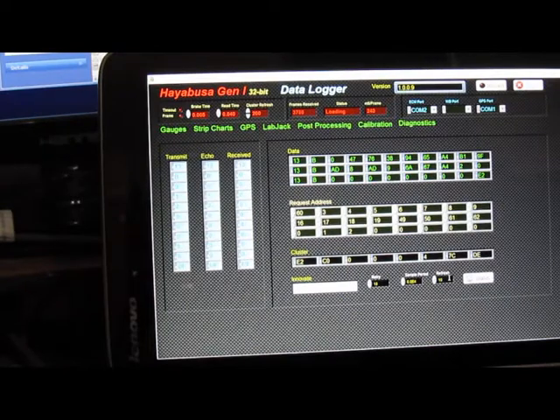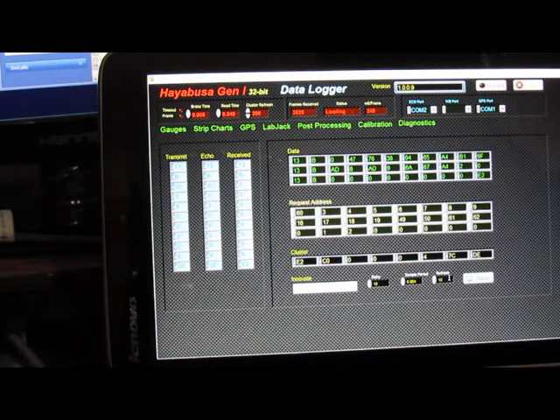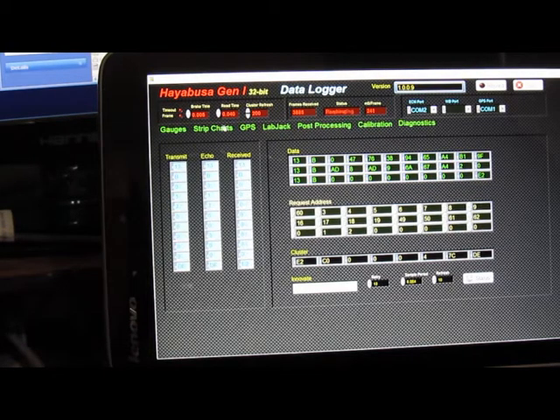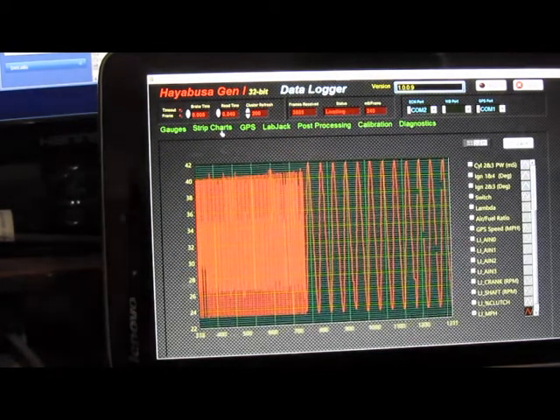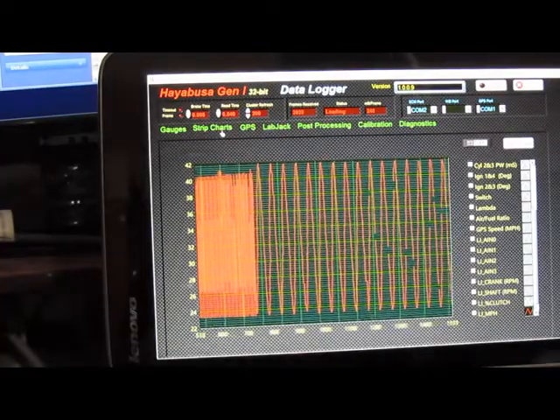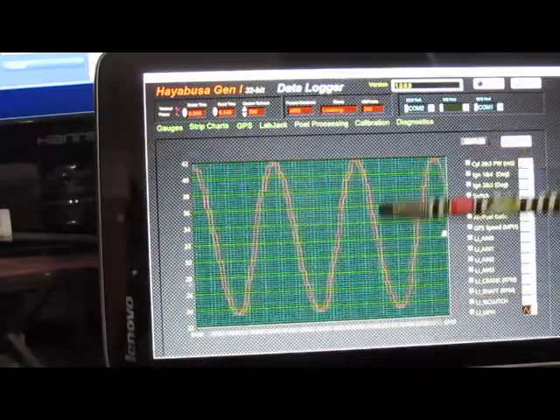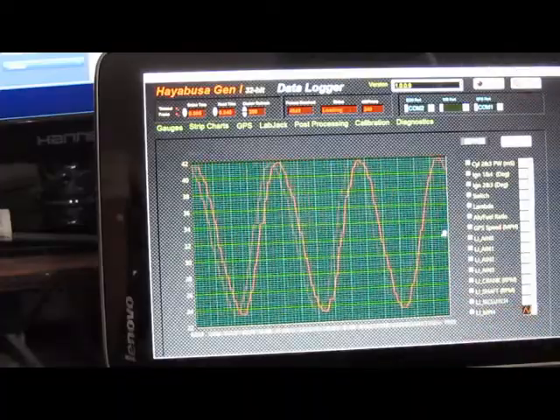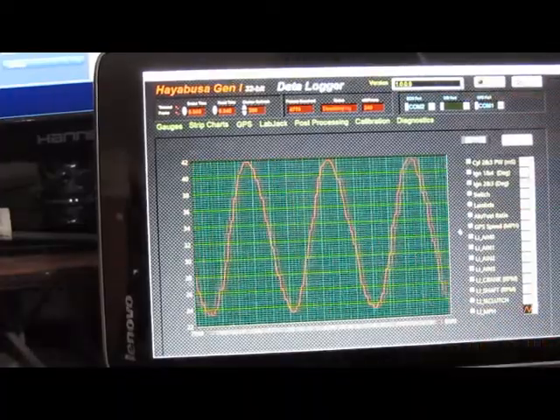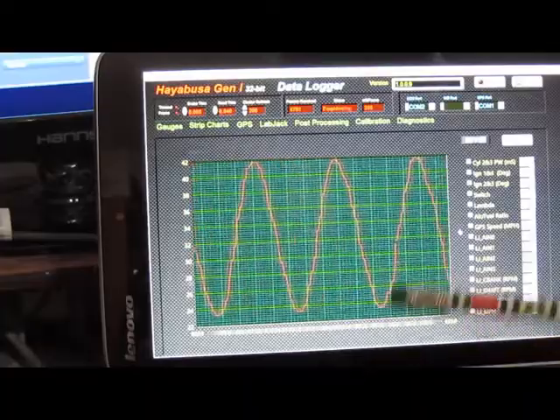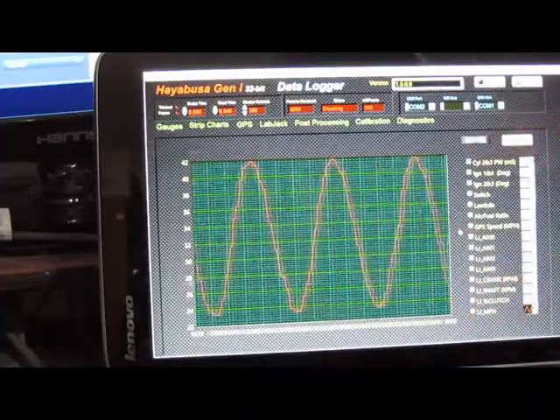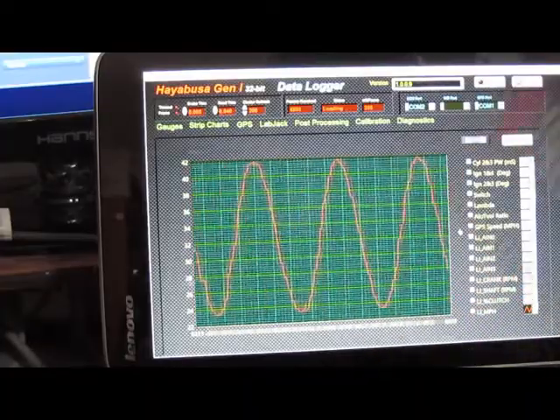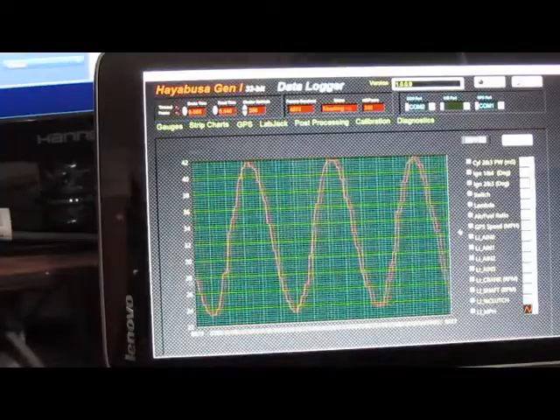What I'm going to do now is change the update rate from 10 times a second to 100 times a second. We can see here what's happened. This sinusoid represents the frequency modulation of the output shaft. The reason that we need this kind of speed is because the motorcycle will actually respond at about this rate when we're looking at the clutch.